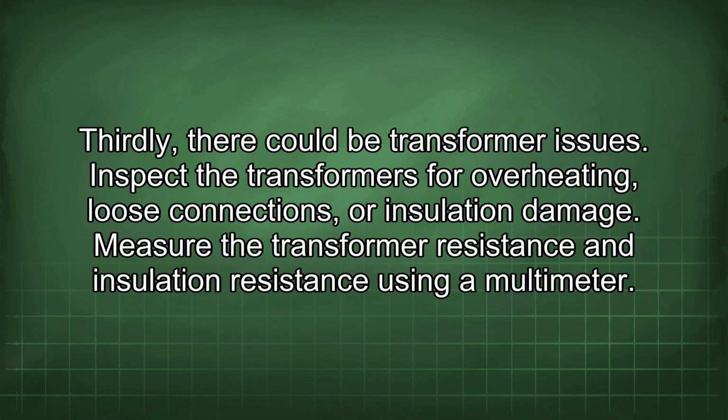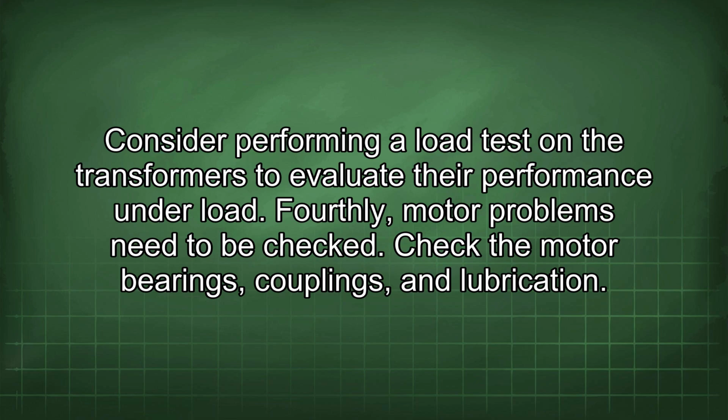Thirdly, there could be transformer issues. Inspect the transformers for overheating, loose connections, or insulation damage. Measure the transformer resistance and insulation resistance using a multimeter. Consider performing a load test on the transformers to evaluate the performance under load.